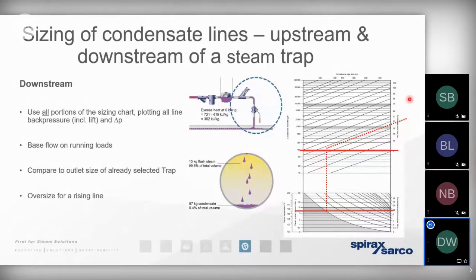And you can see how we would correctly size a condensate pipework at the appropriate mass flow rate, allowing for the pressure drop. Somewhere between 20 and 25 millimeters, depending upon whether the pipe size is climbing away from the steam trap or falling. Now, what you can see is if we'd mistakenly assumed that condensate was a liquid and that there wasn't a phase change, we'd have just taken the horizontal line straight across. And of course, that pipework would be massively undersized. That's where we encounter the vast majority of problems.